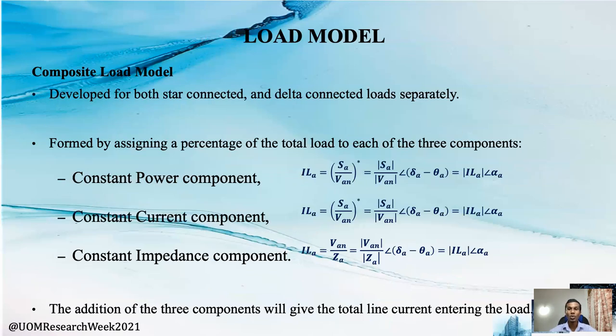For the loads, we used the composite load model because an actual distribution system experiences constant power, constant current, and constant impedance loads at the same time. Load current can be calculated using the equations shown in the slide for constant power, constant current, and constant impedance respectively. Total current drawn by the load can be calculated by assigning a percentage to each of these components.